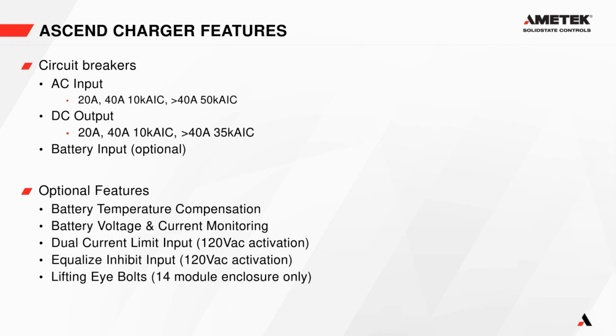Some of the optional features, like we've already talked about temperature compensation, current battery voltage and current monitoring. We also offer a dual current limit input. It's a dry contact that goes into our charger that will limit the output current of the charger if it is closed. This is used usually if you have your batteries in a separate room and an exhaust fan fails. You don't want to charge your batteries too hard, to prevent buildup of hydrogen gas.